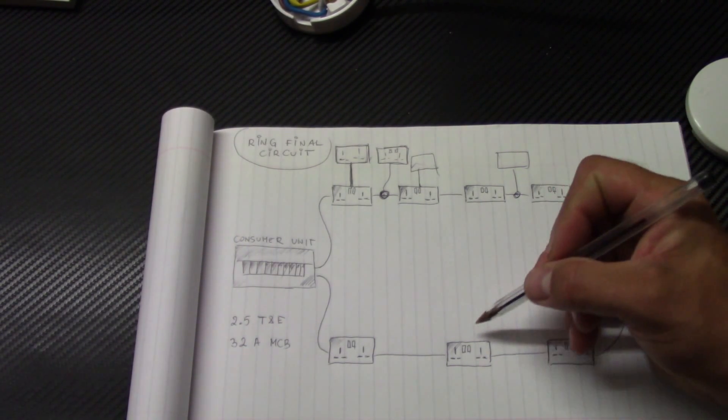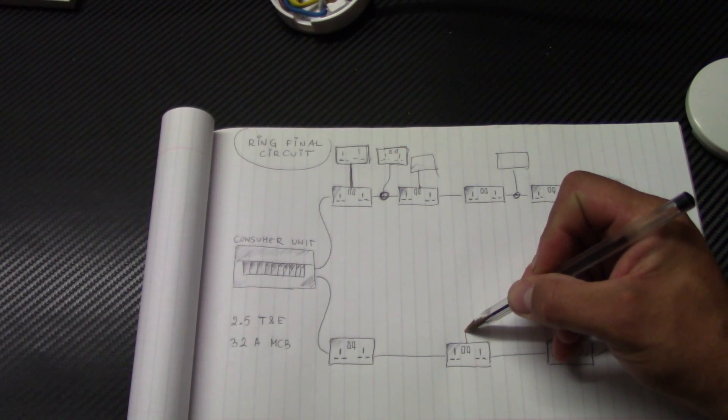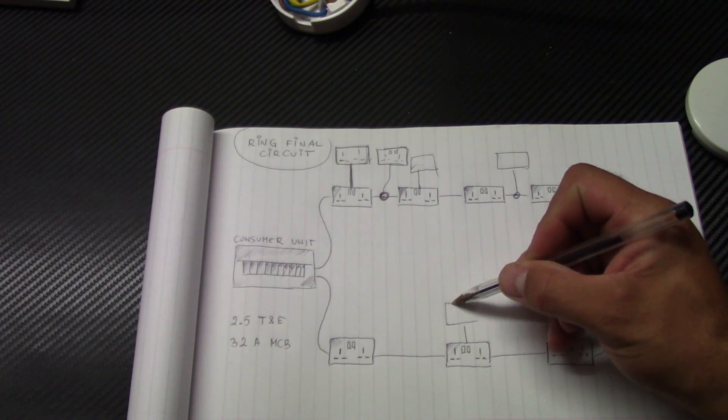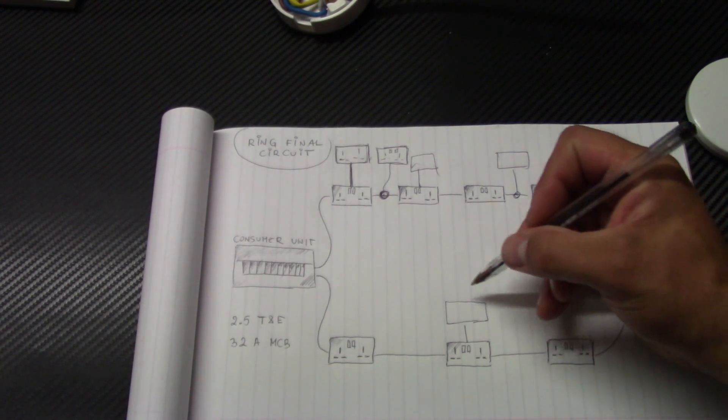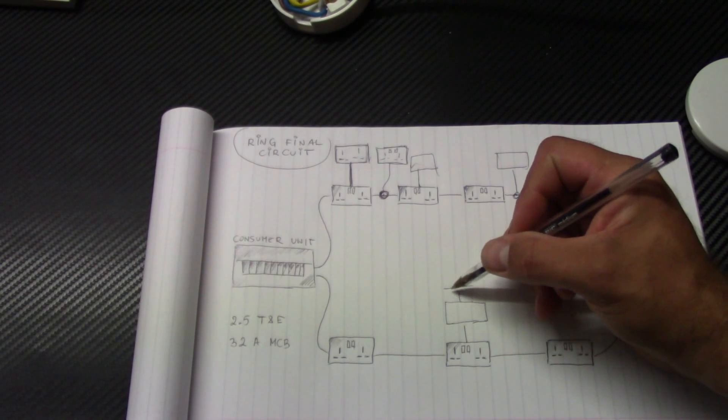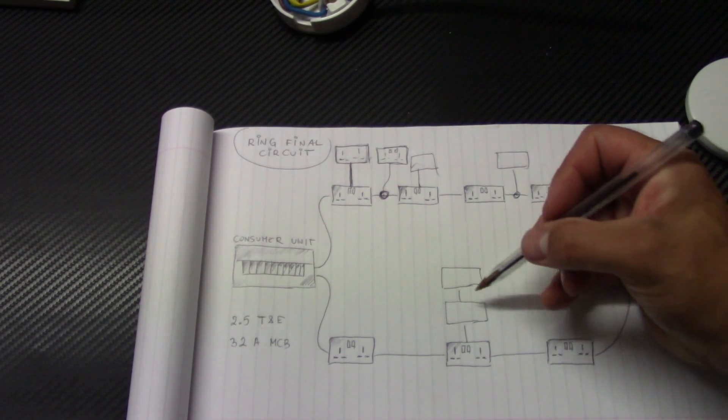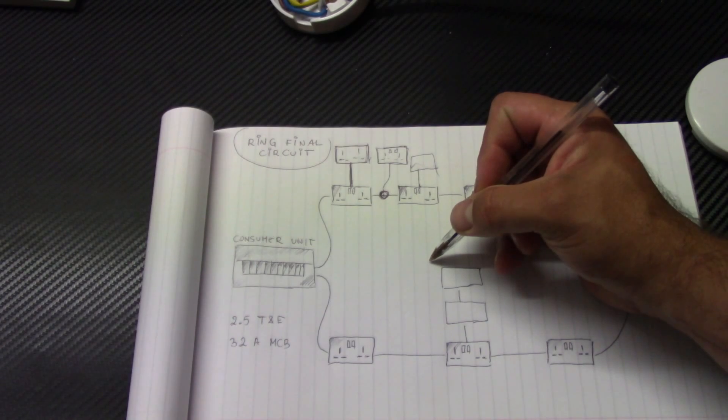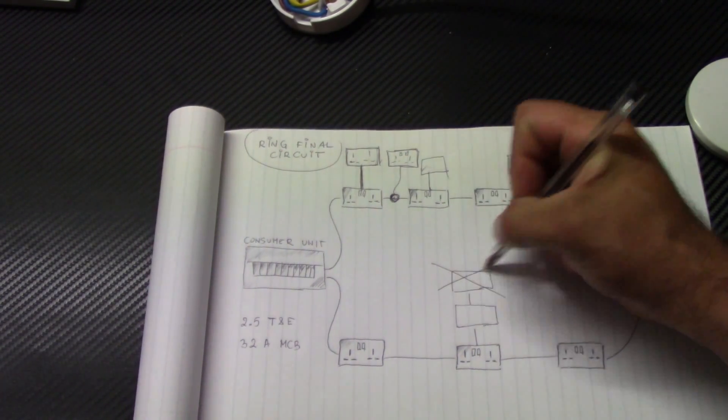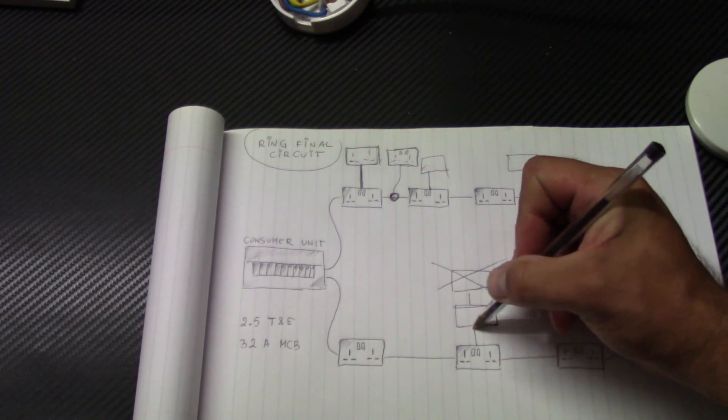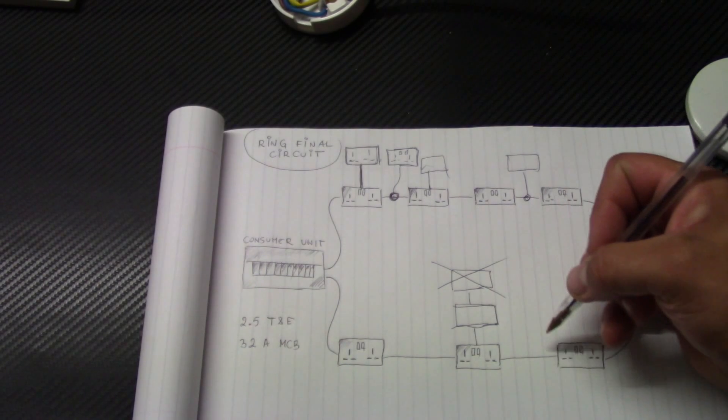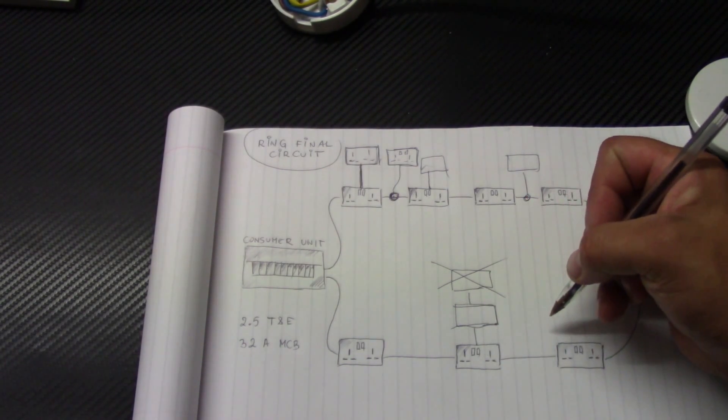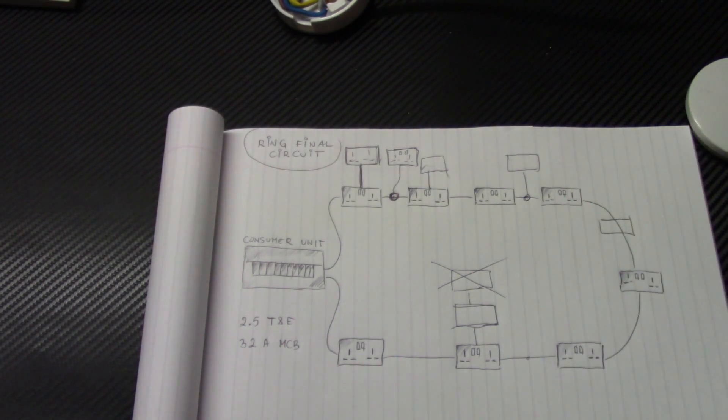One more very important thing. If you make a spare from the socket or from the junction box, you can't have another one just behind this one. This is wrong. This is against the regulations. You can have just one spare from one socket or one unfused spare from the junction box.